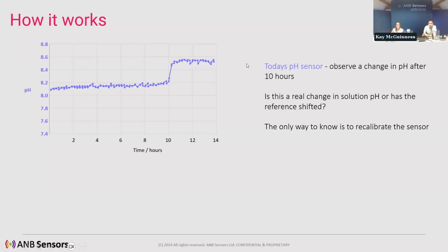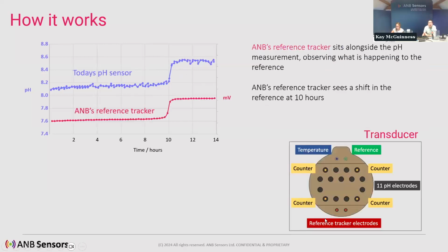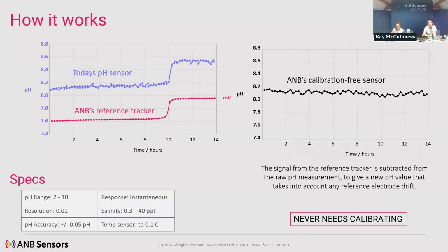We sought to solve this problem by making a calibration-free sensor by basically monitoring the reference potential of the reference electrode in real time and without end-user intervention. Therefore, we can correct it. In the picture here, we show a change in pH or outputted pH around 10 hours. But is that really a change in pH or a change in the reference electrode potential? Our transducers carry an internal reference electrode tracker, which tracks the potential of the reference electrode, a number of pH sensing electrodes for lifetime, and a temperature sensor. By plotting the reference tracker potential with the pH sensing electrode, we can see after 10 hours that isn't a change in pH, rather a change in the reference electrode potential. Therefore, we can correct our outputted pH to give us our calibration-free measurement.